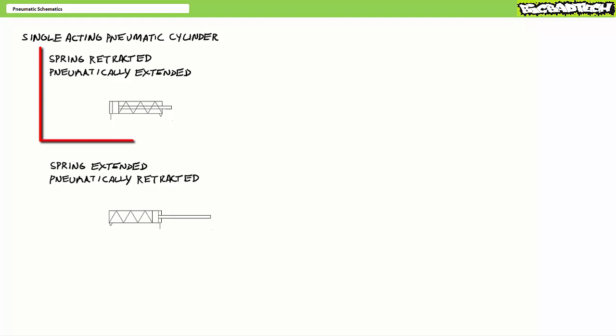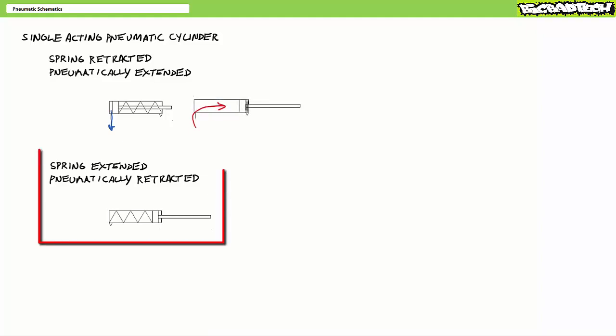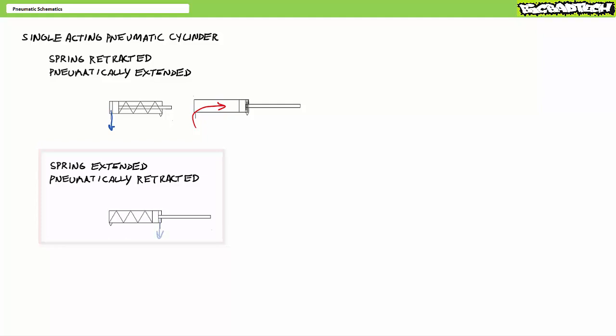Our first cylinder is a spring retracted pneumatically extended single acting cylinder. With no pressure in the cap end, the spring of the rod passively retracts the cylinder. Extension necessitates pressurized flow into the cap end. In contrast, the second single acting pneumatic cylinder is spring extended pneumatically retracted. With no pressure in the rod end, the spring in the cap passively extends the cylinder. Retraction necessitates pressurized flow into the rod end.